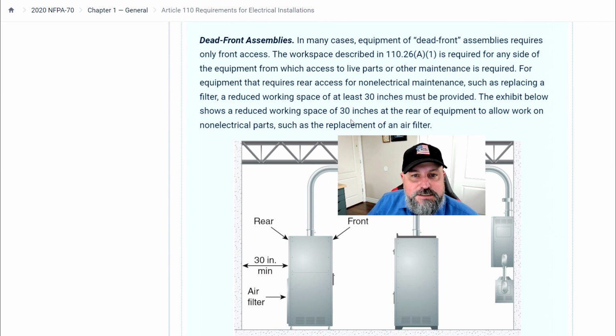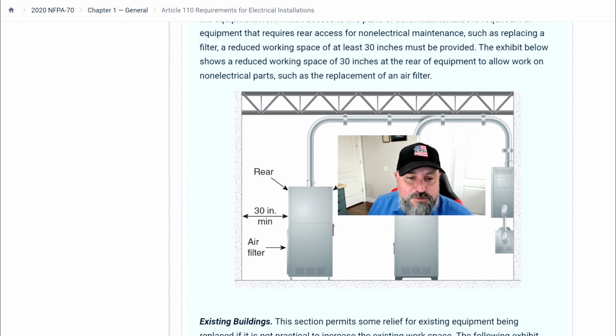Dead front assemblies. In many cases, equipment of dead front assemblies requires only front access. The workspace described in 110.26(A)(1) is required for any side of the equipment from which access to live parts or other maintenance is required. For equipment that requires rear access for non-electrical maintenance, such as replacing a filter, a reduced working space of at least 30 inches must be provided. The exhibit below shows reduced working space of 30 inches at the rear of the equipment to allow work on non-electrical parts such as replacement of air filters.